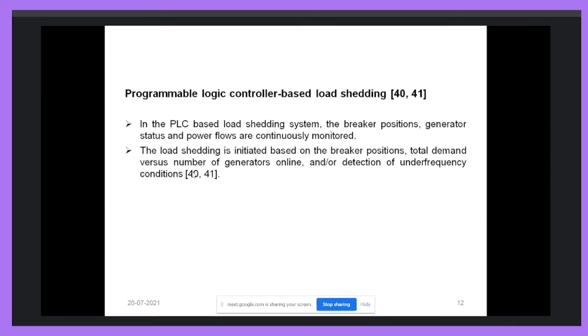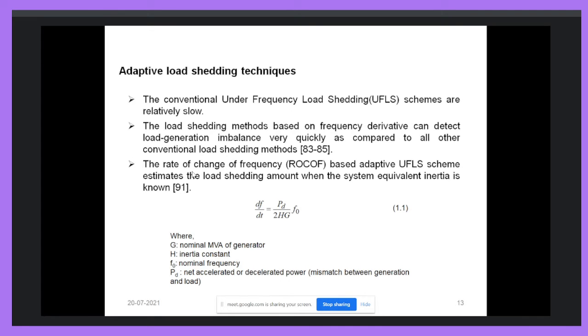Also, the programmable logic controller based load shedding scheme is there, in which we set the generation and load, the breaker position, generator status and power flow. We continuously monitor the power flow, but these are also designed for the worst operating condition. The load shedding is initiated based on the breaker position monitored by the PLC system, the total demand versus the number of generators online, and detection of under frequency conditions. Now, these were the conventional load shedding schemes. Now we discuss adaptive load shedding.